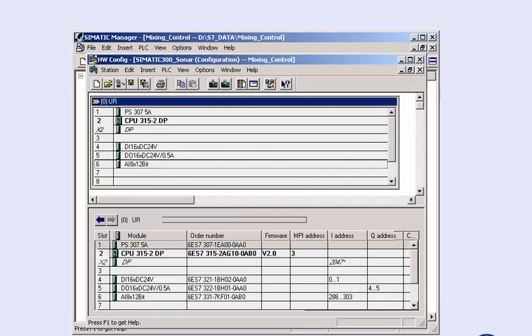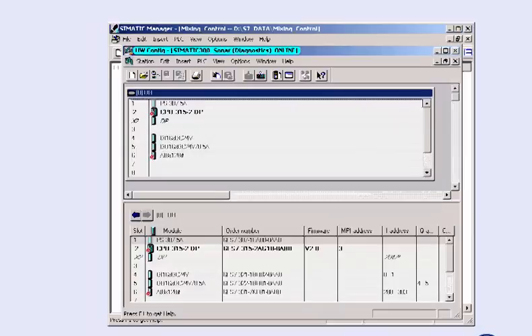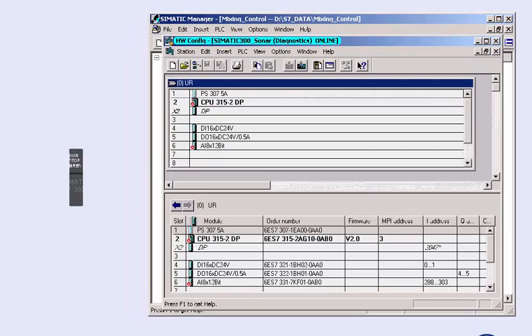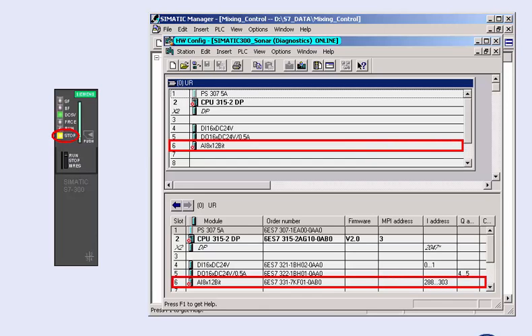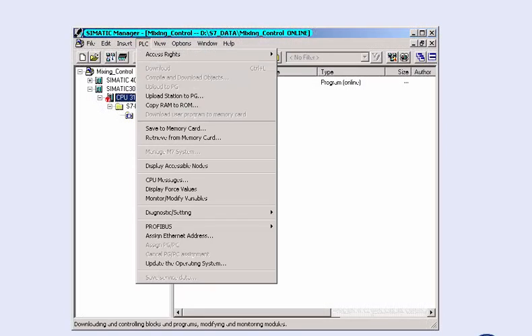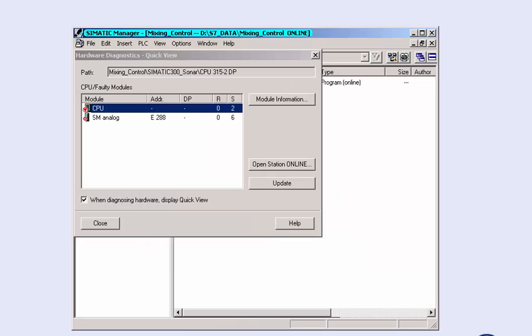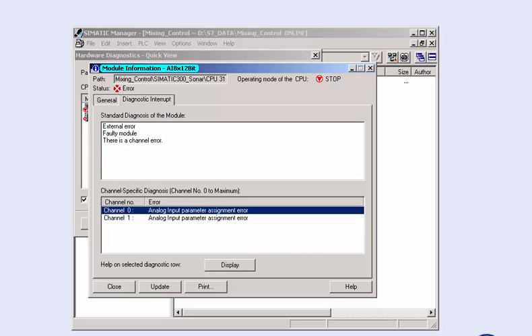After switching on during startup, the CPU compares the configured set point configuration with the actual configuration. In our example, the CPU is programmed to immediately change to stop mode if there is any deviation. In this case, it is a definite indicator that the actual hardware setup differs from that specified by the project planner. With its detailed diagnostics options, the SIMATIC manager shows a quick overview of the causes of the CPU stop and subsequently offers a detailed error analysis. In the window for diagnostic interrupts, you see that the stop cause is a configuration error of channels 0 and 1.